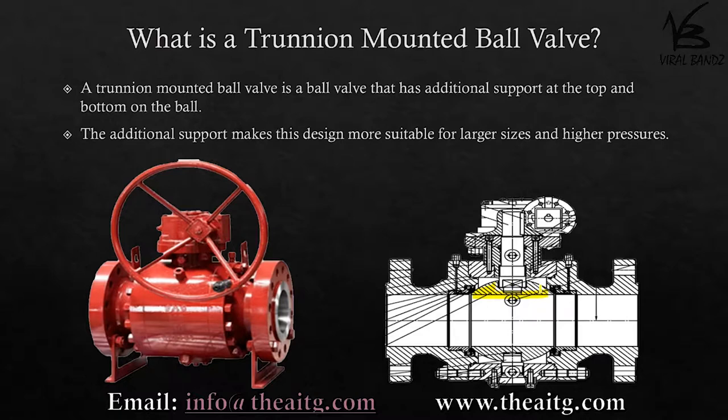has a slot for the stem, similar to the floating ball valve, but if you look at the bottom there is also a slot for the trunnion.